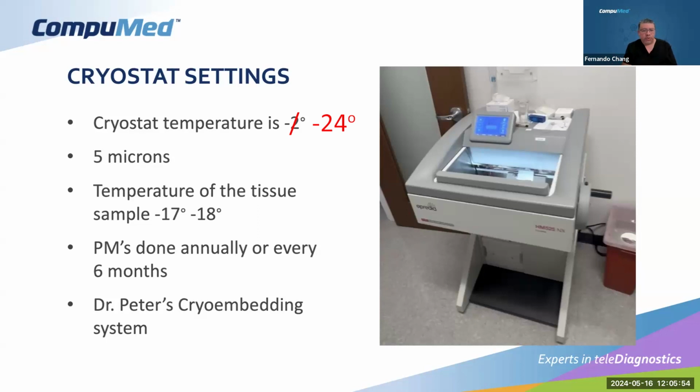And if we introduce a variable that is completely different, in this case a different type of tissue, let's say kidney, which obviously filters blood and water, and blood has water, we'll be knowing that our standard temperature is something that we set up in the cryostat. Facing kidney tissue will make a difference compared to, for instance, liver tissue, which has a little bit less water content. But the variable that is the temperature remains the same, and that's important to keep.